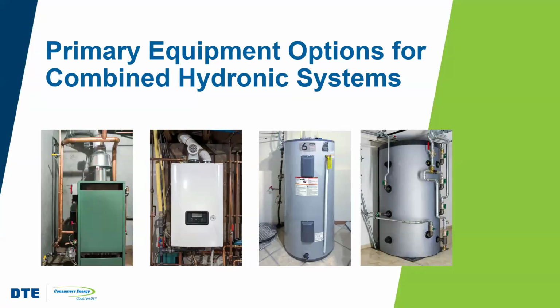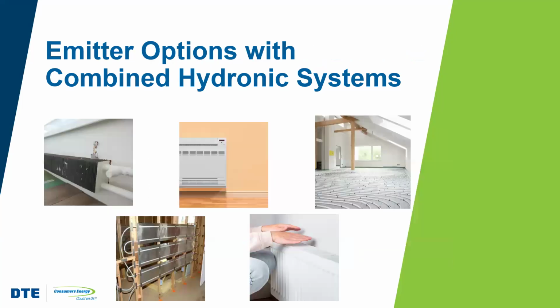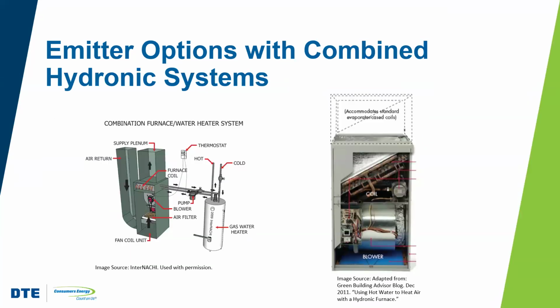With these systems, you typically have a high efficiency heat source. So you've got a water heater or a boiler. You could have a storage tank water heater, you could have a ground source heat pump unit, or you could have a heat pump water heater, right? These things also can be combined with any of the emitters that we've previously talked about, right? One of the things that we haven't talked about, though, is the hydronic furnace or the water furnace, or the air handler as we would call it in commercial spaces, right?